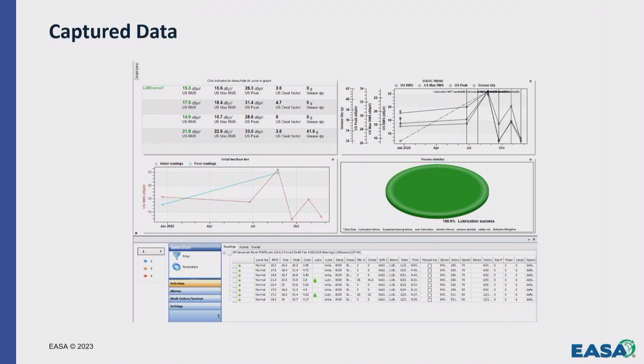Every application is so specific, and we've found that quite often some bearings don't require lubrication very often. Some do, especially when you start getting 3,600 RPM motors. Those are going to need it a little bit more often. But yeah, I would say a pretty large difference between those. Yes, I would say so, because the OEM interval is just kind of a set amount that they're going to tell you to give. So yeah, it's really amazing. Some of these motors, we'll be talking with our customers and hearing how much grease they've been adding, and we often find we're adding much less than what they're adding, based on that OEM time-based interval.